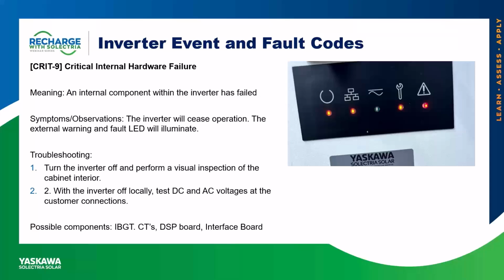The next code we'll be discussing is CRIT9, Critical Internal Hardware Failure. In contrast to previous codes, there isn't really a definition, as the code for the most part speaks for itself. Essentially, an internal component within the inverter has failed. Symptoms and observations you might expect to see at this point will be, for one, the inverter will cease operation, and the external warning and fault LED will illuminate.